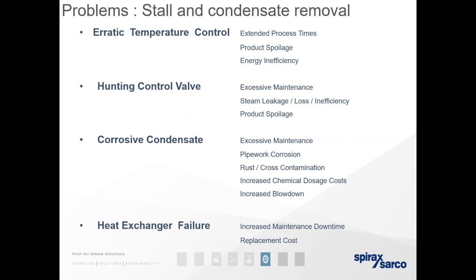Hunting of control valves is a major indication. So if you see a control valve opening and closing, moving around instead of being very steady, that's an indication that you have a challenge there with either stall or condensate. Steam leakage, loss, inefficiency. So again, as we covered with leaking traps and product spoilage. Corrosive condensate, so excessive maintenance, as we touched upon earlier. If you're seeing your traps needing to be repaired more often, more leaking traps, more traps failing open or closed. Pipework corrosion, as we spoke about before in the previous question.